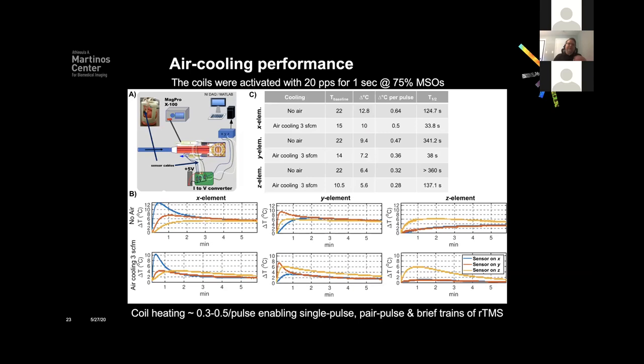The second thing we checked was heating. Smaller coils tend to be more tightly wound with smaller diameter wire, so we used the air cooling approach — injecting air into the coil and giving a brief train of pulses, then observing the temperature rise. With air cooling, coil heating is approximately 0.3 to 0.5 degrees per pulse. More importantly, with air cooling the temperature returns quite nicely after a minute — not exactly to baseline, but enough to start another rTMS round. So with this simple cooling design we can run single pulses, spaced pulses, and brief rTMS trains. Liquid cooling would be more efficient, but for our first approach and the goal of using this inside the MR, we went with basic air cooling.